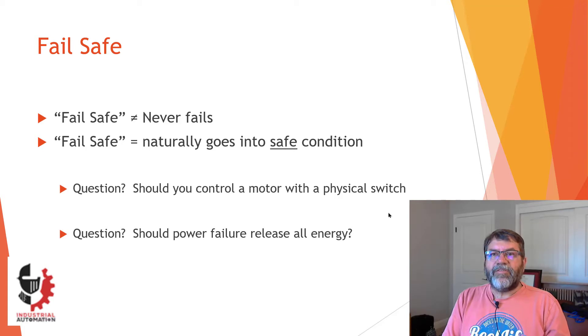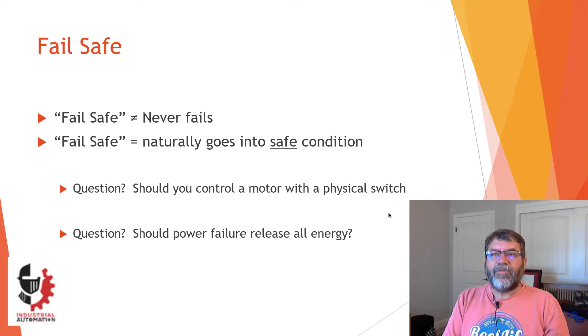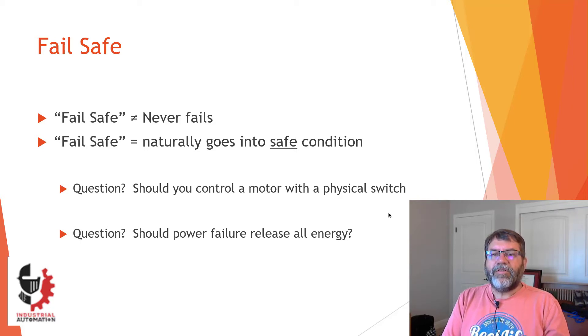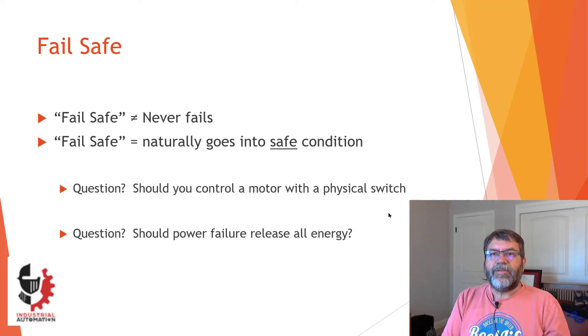There are some questions you have to ask yourself when doing your programming, such as: should you use a switch to control a motor? If you set a switch to the on position, should that directly control the motor, or should that latch a contact inside your logic — and that contact has to be re-latched every time for that motor to start? In some cases you want that, like with a table saw, which should not start on power up if the switch is on.